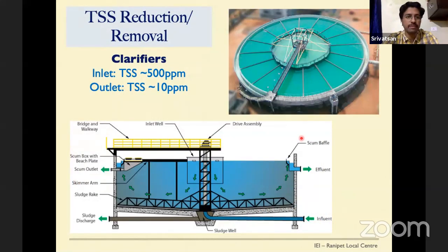So here we have some pictures of systems which are involved in total suspended solids removal. This is the first one, the clarifier. This is used in the pre-treatment plant. It is basically a civil construction tank wherein influent water is passed into the center and goes through this cycle. We allow the water a lot of contact time with the coagulating chemicals and allow it to settle in this clarifier basin.